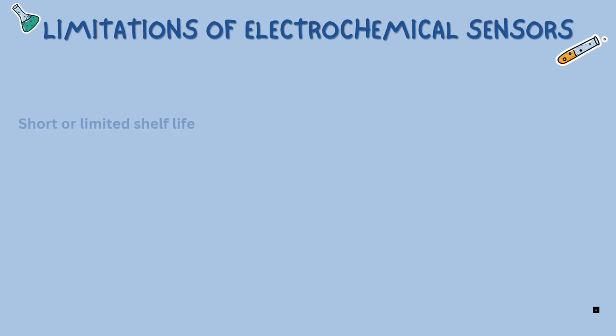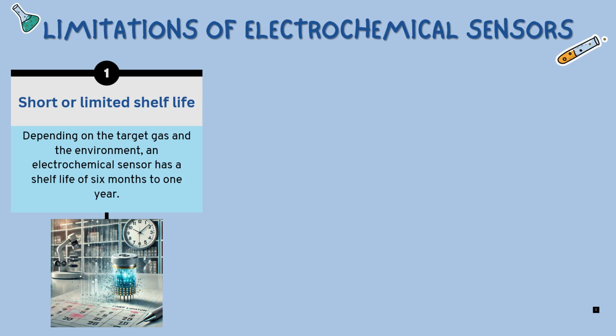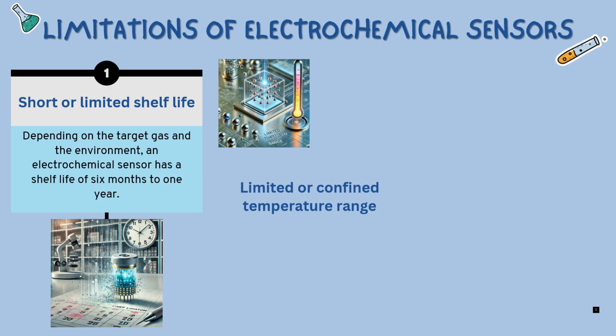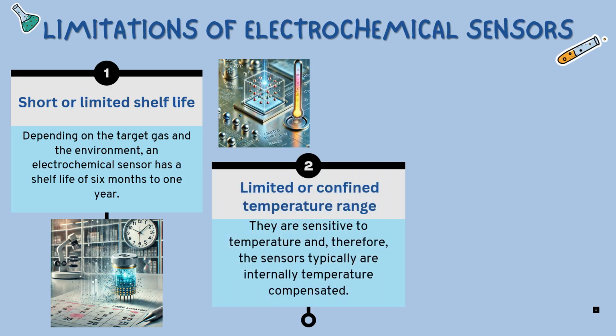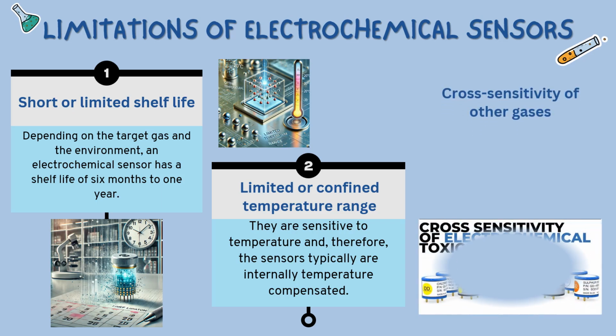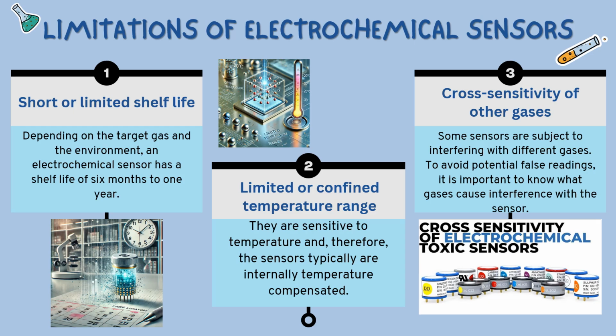Limitations of electrochemical sensors. The first limitation of electrochemical sensors is short or limited shelf life. Depending on the target gas and the environment, an electrochemical sensor has a shelf life of 6 months to 1 year. The second limitation is limited or confined temperature range. Temperature is a big factor for electrochemical sensors, and they are sensitive to temperature, and therefore the sensors are internally temperature compensated. The last limitation is cross-sensitivity to other gases. Although this is an advantage, it tends to be a disadvantage too. Some sensors are subject to interference from different gases. To avoid potential false readings, it is important to know what gases cause interference with the sensor.